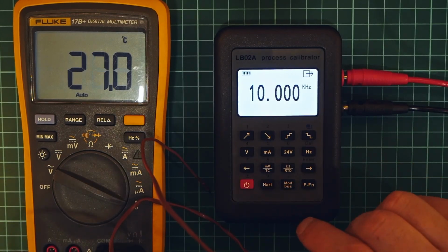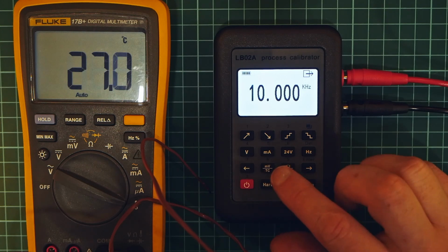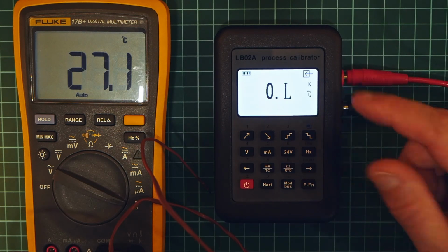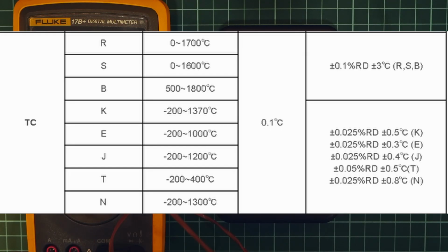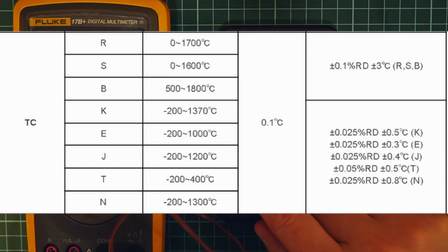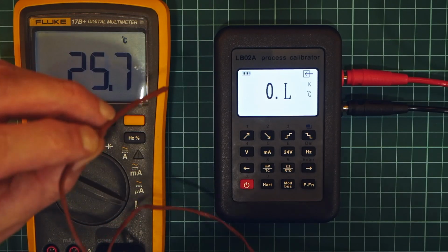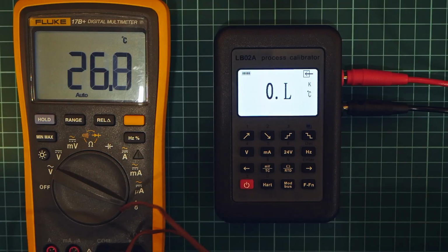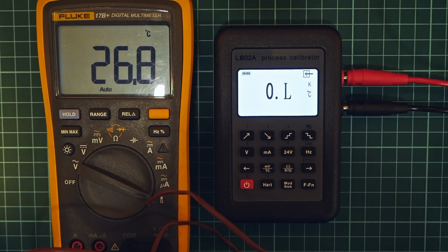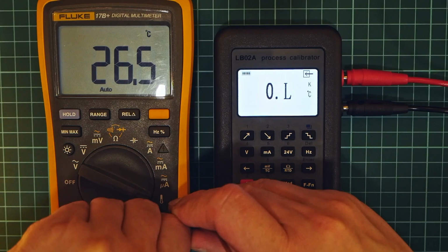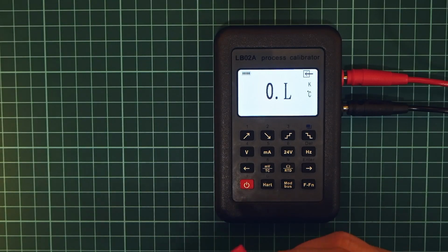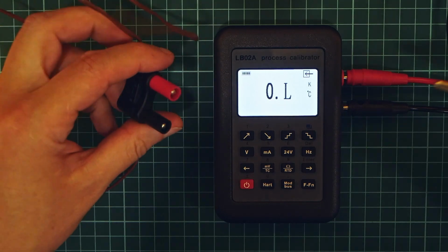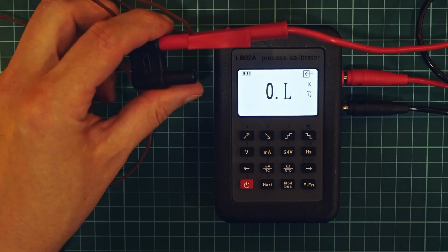Let's jump to millivolt and thermocouple mode. We press this, and right now we are in input mode, and we can scroll with these arrows and change what kind of, well, basically thermocouple we want to measure. So right now I have this K-type thermocouple with my Fluke, temperature 26.8 Celsius. We can remove this thermocouple and we can test it with this process calibrator.